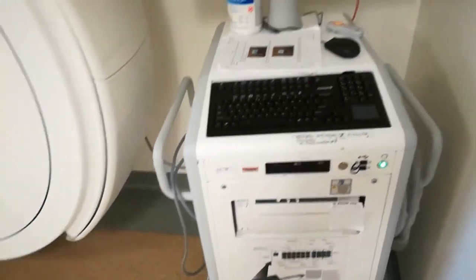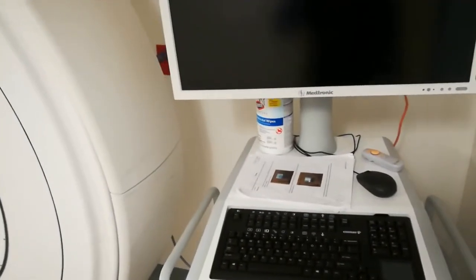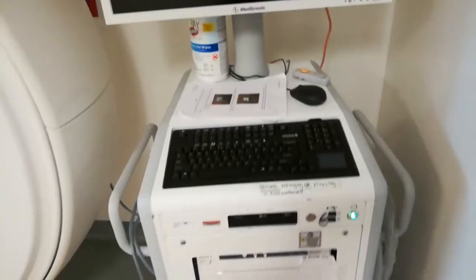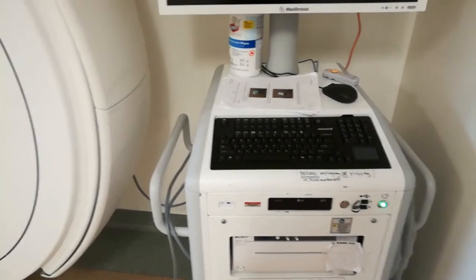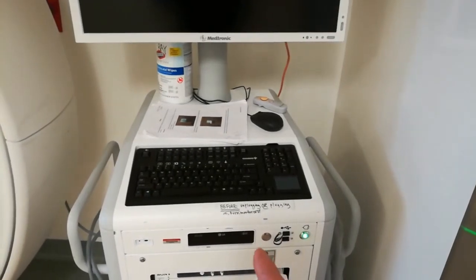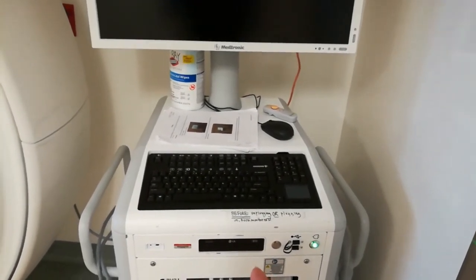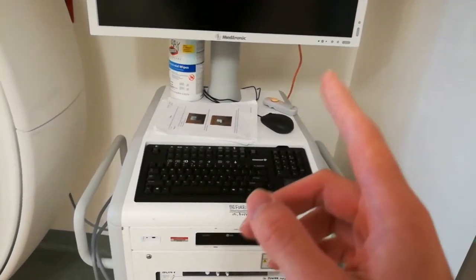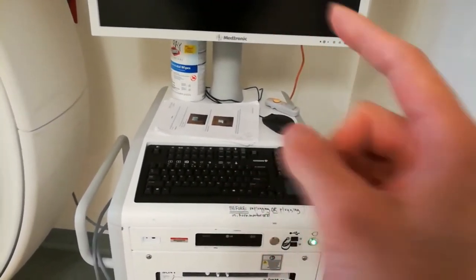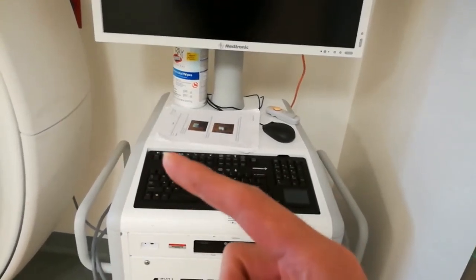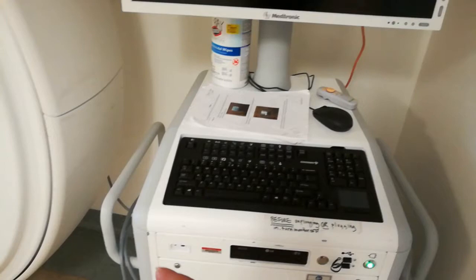But what you must remember for the O-arm, if you take nothing else away, is to make sure you plug it back in after you use it, otherwise this thing will run out of batteries. And always, always, always, never unplug the monitor, the workstation here, from the wall when it's still turned on. And before you do the 3D spin, make sure that orange cord or whatever covered cord linking the workstation and the Medtronic machine is plugged into each other before you do the 3D spin. Otherwise, you pretty much did the spin and there's no way we can transfer the images from here onto their monitor or onto their Medtronic machine.